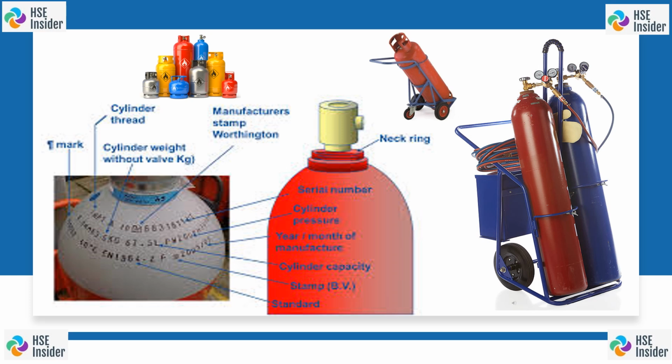Then the storage of cylinders. The cylinders shall be stored in a cool, dry, ventilated place under cover, away from boilers, open flames, steam pipes, or any potential sources of heat. The storage room or shed shall be fire resistant in construction.